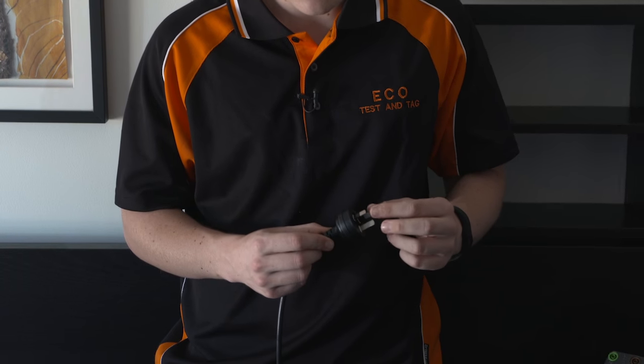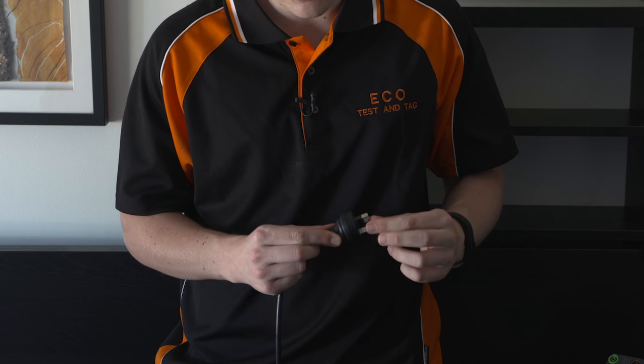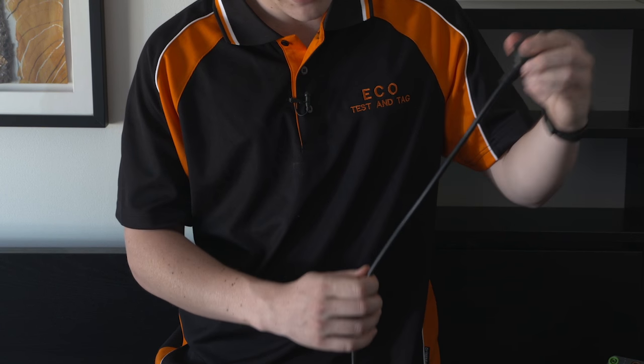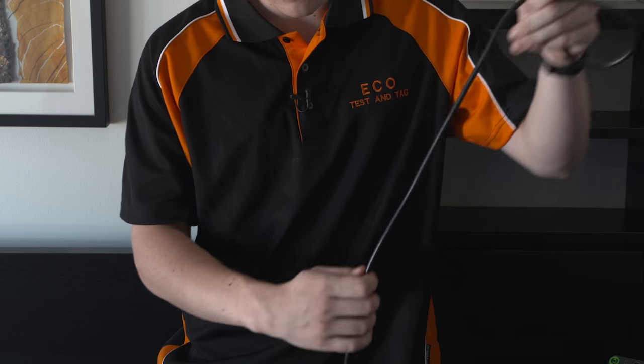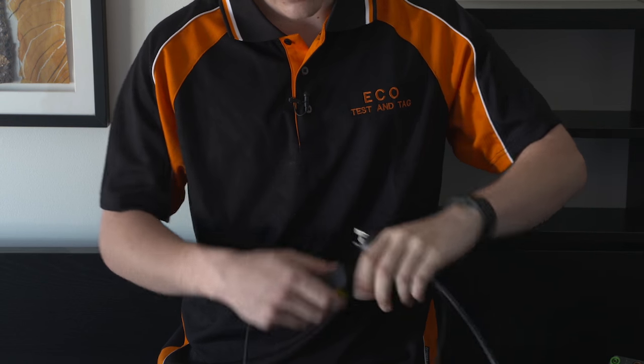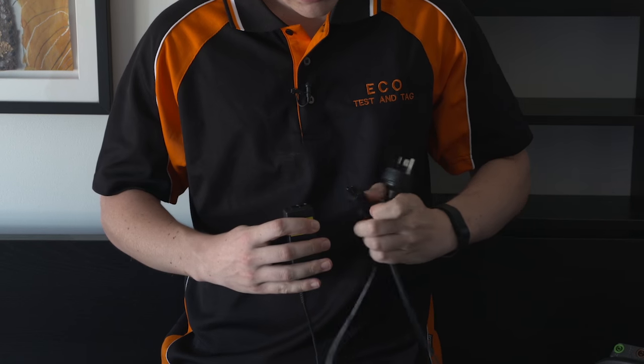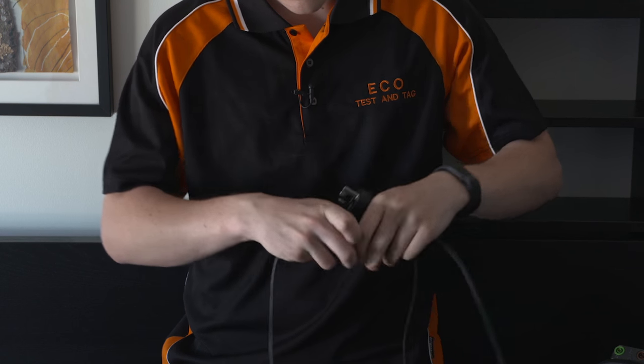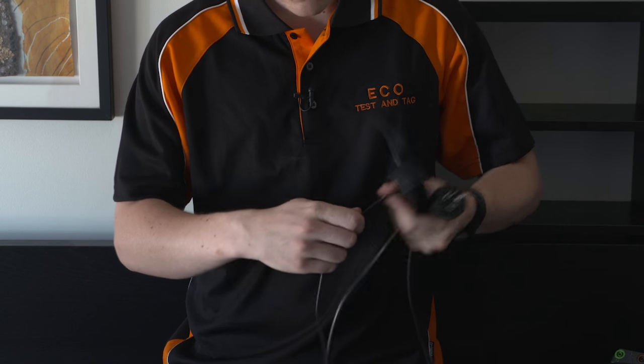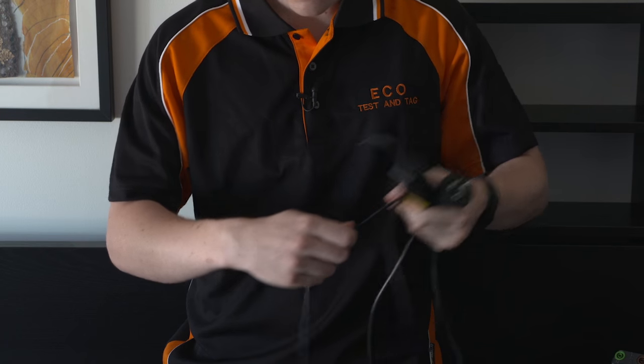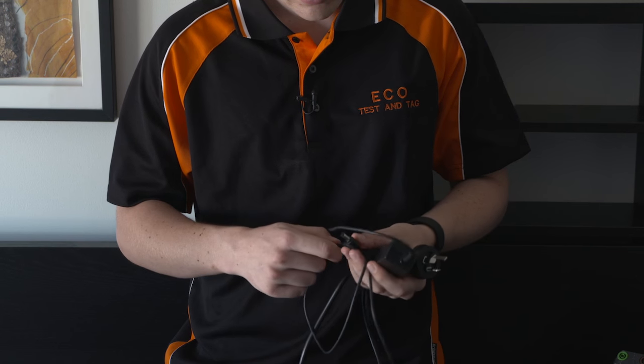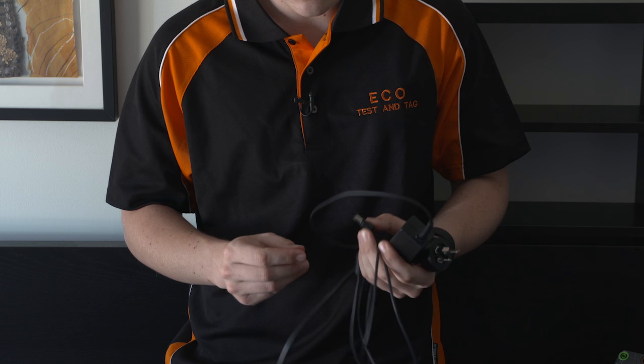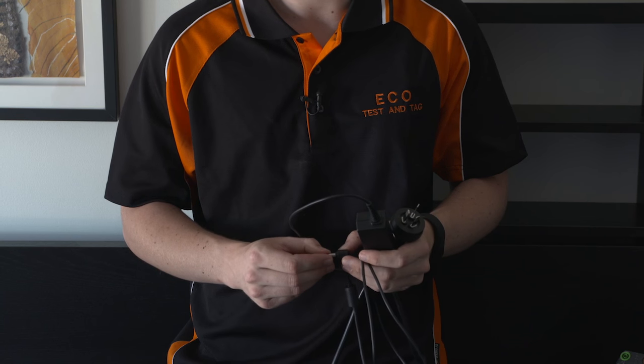The first part to the testing process is the visual inspection. When visually inspecting an item, you want to ensure the pins are secure, and there is no visible damage, frays, or blemishes to the lead or the case. Once the visual inspection is complete, you move on to the next step.